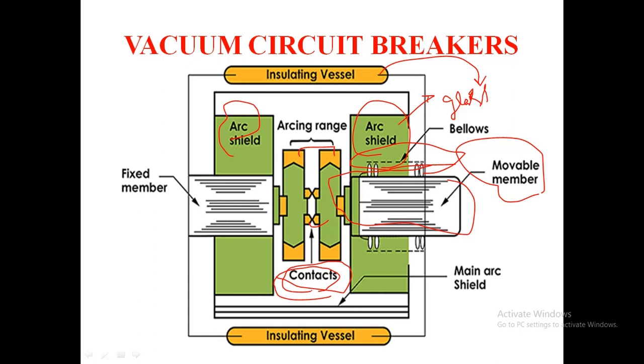The arc interruption process in a vacuum interrupter is different from other types of circuit breakers. The separation of contacts releases vapor, which fills the contact space. It contains positive ions liberated from the contact material, and mainly depends on the current in the arc. When the current decreases, the rate of vapor release decreases. After that, the current will be zero.